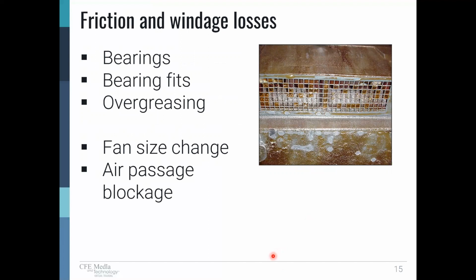Friction and windage losses. We have bearings and friction losses in the bearings, especially rolling element bearings. Bearing fits, if the fit's too tight, that increases the friction losses. Over-greasing, too much lubricant, too much grease in the bearing, also increases friction losses. Fan size: if we've got a fan on the motor, a cooling fan, it needs to be replaced really exactly in kind. We don't want to make the fan larger. It'll move more air theoretically, but that increases our windage loss. If we make it smaller, it'll move less air, but then the winding's going to probably run too hot and possibly even the bearings.